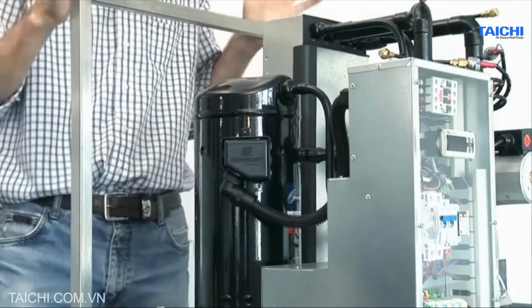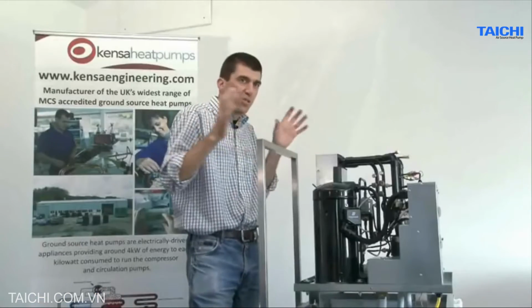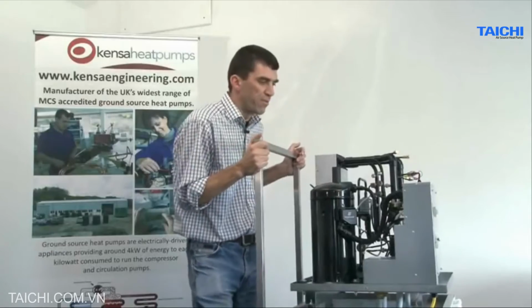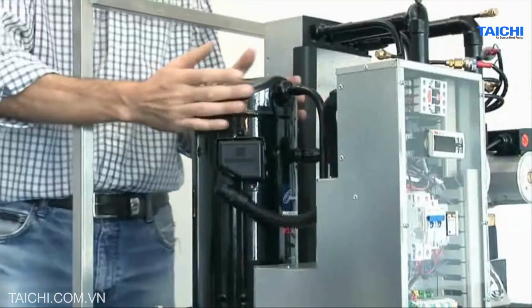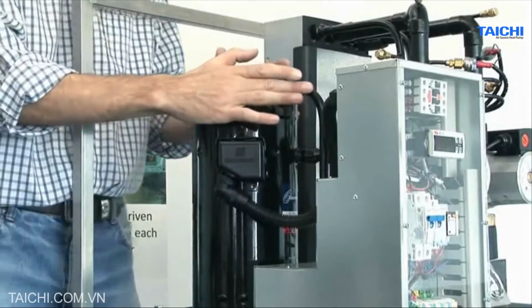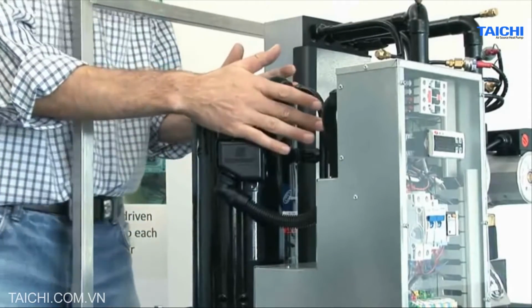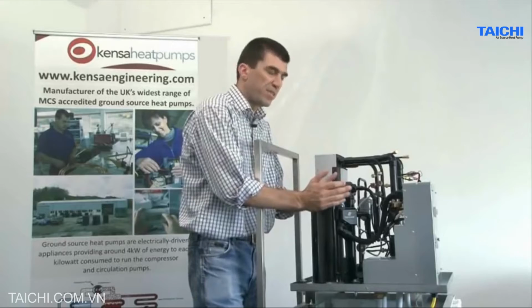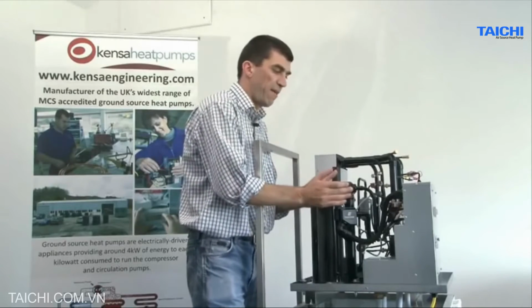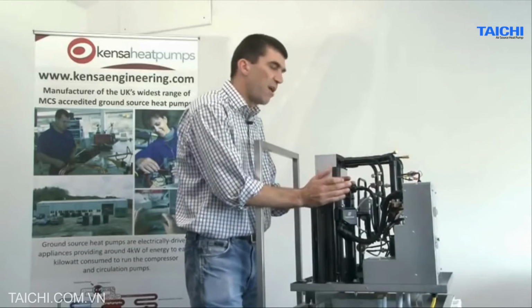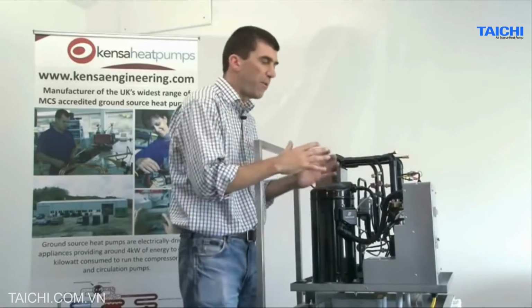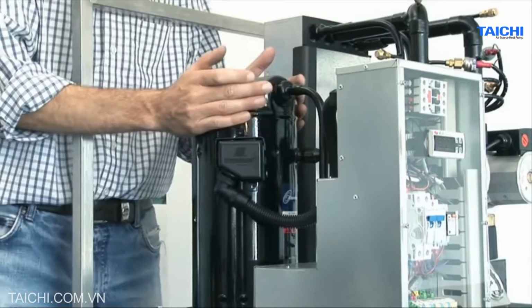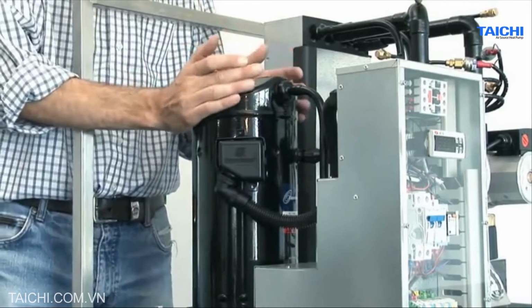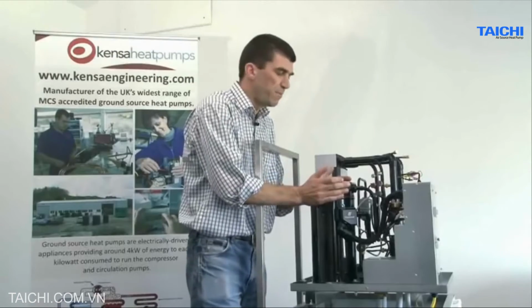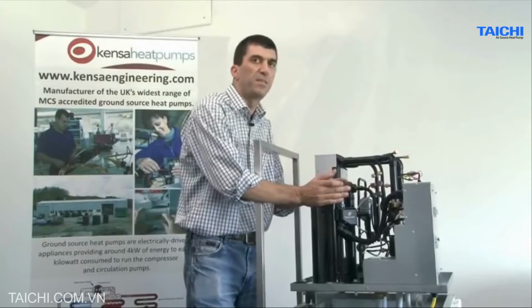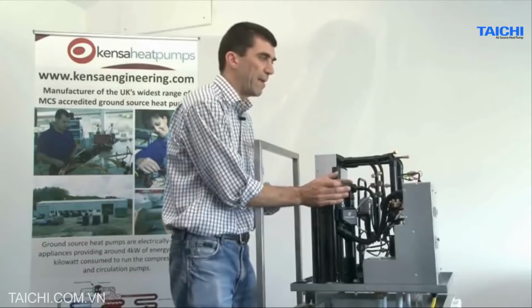So with an endless circuit, there's no obvious place to start or stop talking about what's going on with the refrigerant. But I think the easiest place to start is the discharge from the compressor. This is the outlet from the compressor. The compressor only ever sees gas, as in a vapor, whereas the refrigerant itself exists in 2 forms, both liquid and gas, vapor. We achieve the effect of pumping heat by repeatedly changing the refrigerant from a liquid to a vapor and back to a liquid again.